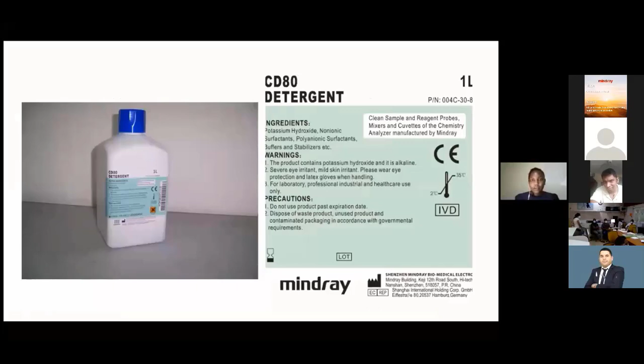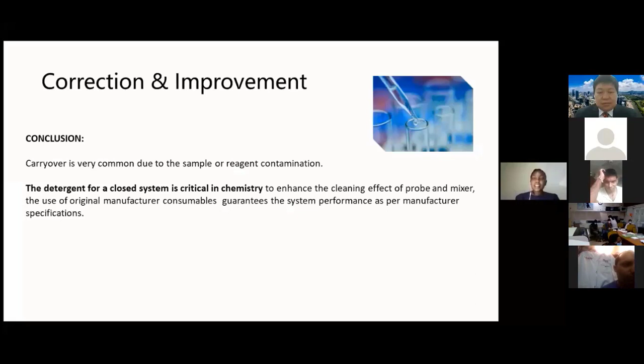Carryover is very common. It just happens in our labs every now and then, and we should be keen to realize it and at times fix it and identify what could be the issue, for quality results, good reproducibility, quality diagnosis and such. In this case, the detergent for a closed system is really critical in chemistry because it will enhance the cleaning effect of the probe and mixer. And it is recommended that we use original manufacturer consumables because they guarantee the system performance as per the manufacturer specifications. I think that was our case study, and we're happy we fixed it.